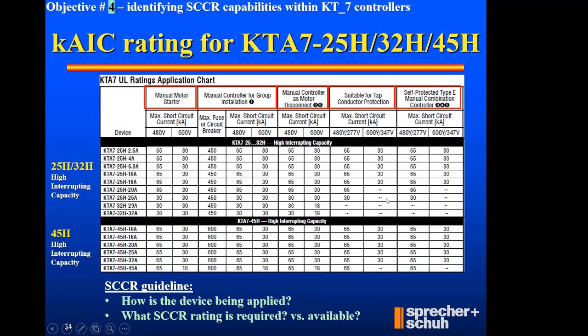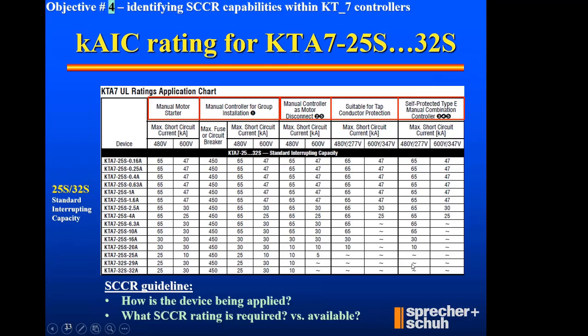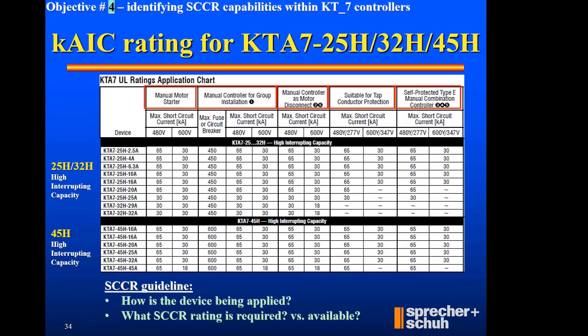And then previously on the 25S, I back up and say, if I had a 15 horse 460 volt motor drawing 21 amps, this 25 model is not going to carry a type E approval. I've got to go to the 25H-25A for 21 amps. Now I can be self-protected type E. So just knowing how to use this table for the approvals, that was an example.